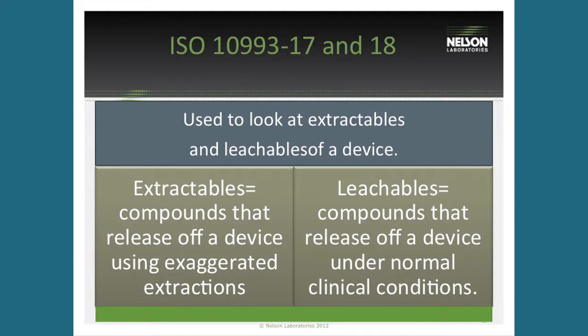The last thing — and I think this might be the most impactful — is looking at in vitro alternatives for biocompatibility. We had great discussions on some testing coming down the pipeline for an in vitro sensitization and irritation test. This means that, once validated, there might be an in vitro alternative to the maximization test and the intracutaneous reactivity test. This is great news because right now the maximization test takes about eight to nine weeks to run, whereas the in vitro version looks to be shorter. Europe has already validated these two methods for cosmetics, and we're looking at piggybacking that validation for medical device extracts.